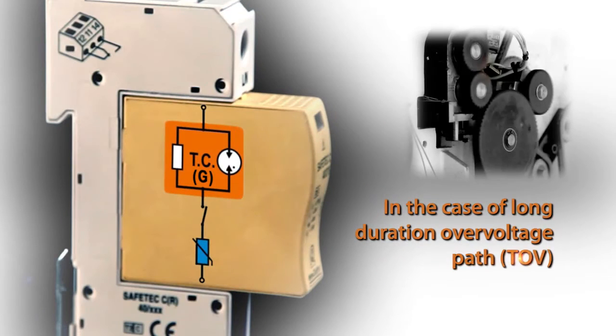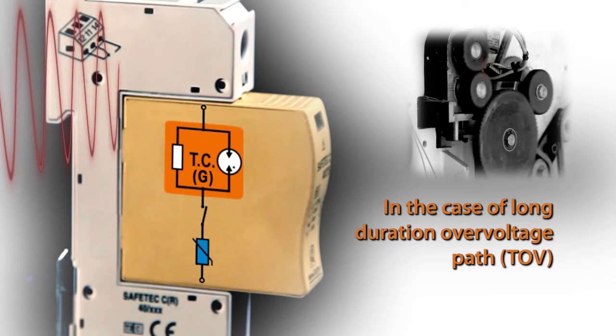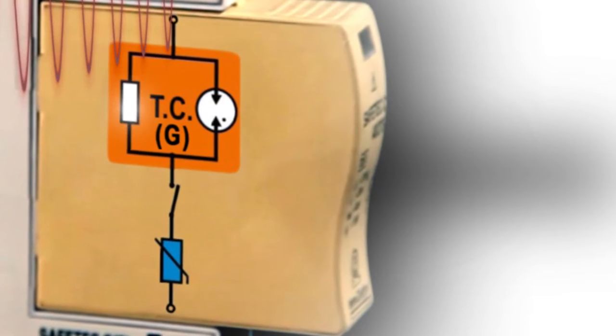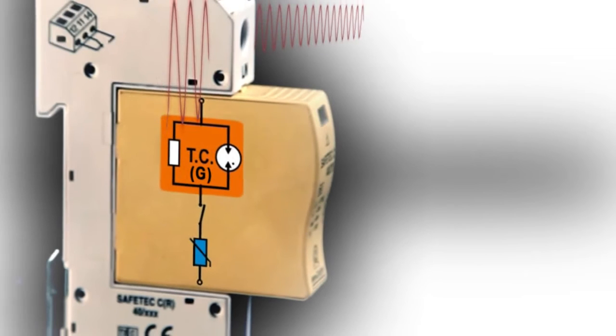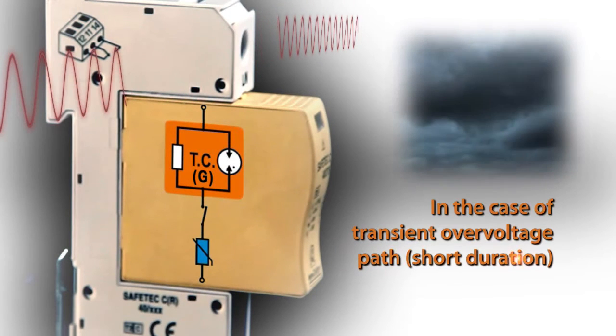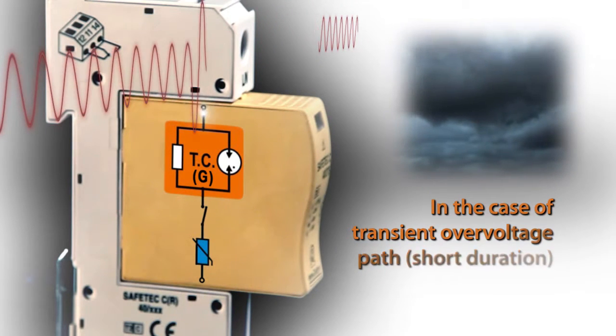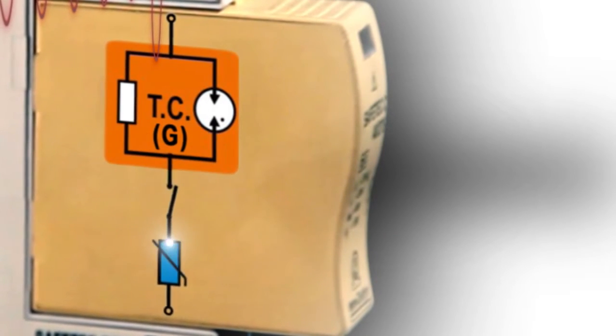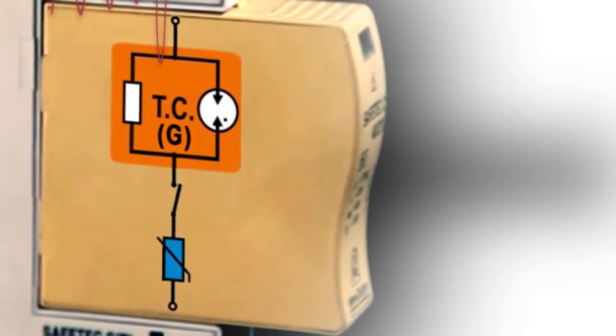In the event of an increased voltage level, the current limiter circuit will reduce the current flowing through the MOV. When normal conditions are re-established, the surge arrestor will continue to perform its normal function. The gas tube surge arrestor and MOV have extremely short response times, as reflected in the low protective residual voltage level. This provides an efficient protection.